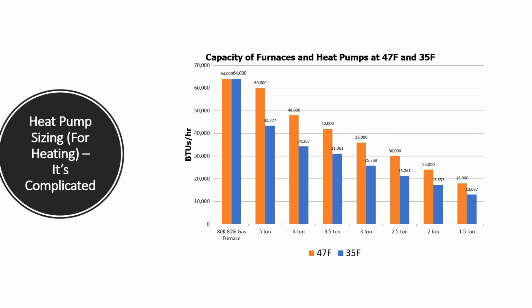So this chart just sort of reinforces what I said before, is that here we have a furnace in orange, and we can see at 47 degrees, which is the orange color, it'll give you 64,000 BTUs. And sure enough, when it's 35, it gives you 64,000 BTUs. But a 5-ton heat pump at 47 degrees would probably give you something close to a 60K. At 35, you're honestly down to almost a 3.5-ton unit.